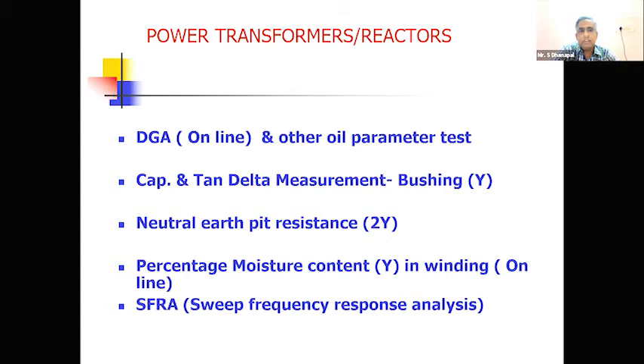But still, we feel that many online techniques can be invented and innovated, but it is not taking shape. For example, fiber optic winding temperature sensors have been invented for our power transformers, but still it is not taking shape. We are not able to achieve any result in finding incipient or budding faults in transformers. Similarly, for circuit breakers, there are still no online condition monitoring techniques. We have numerous vendors manufacturing indigenously in India, but still they are not able to monitor. Only offline techniques are available.